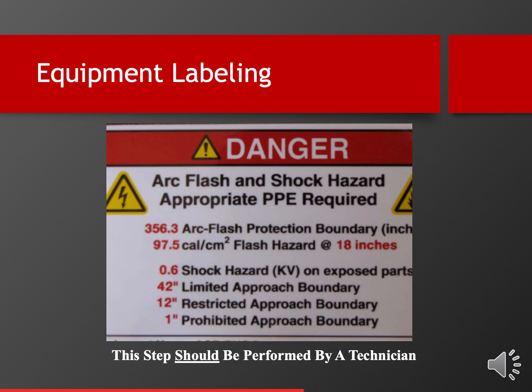Now be aware, arc flash labels are required anytime there's a piece of equipment that would require servicing or maintenance in the field. So if it's going to be accessed in the field, it really needs to have an arc flash label on it. And the information that you see on the label is stipulated in the 70E. And this step, I said, should be performed by a technician, meaning installing the labels, because once again, the electricians have a much better grip on the names of the equipment in the field.